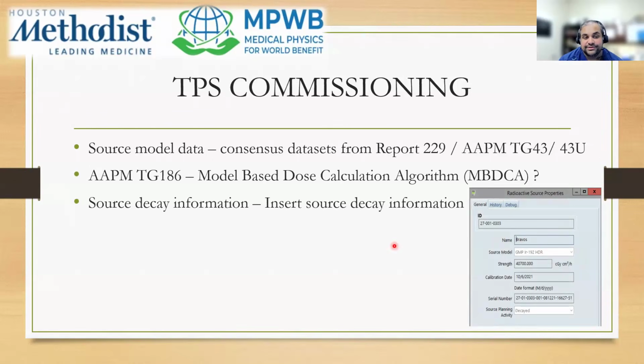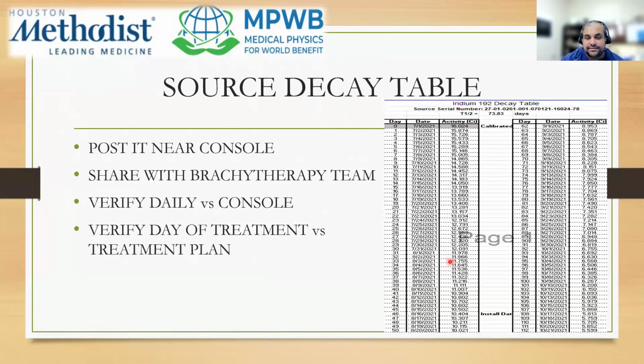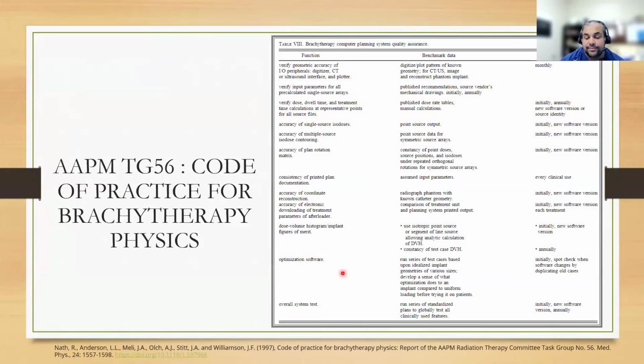You have to import your source decay information into your treatment planning system. This option, I know this is with Varian at least, lets you choose between decayed and nominal. The main difference is that if you leave it at nominal, then all your treatment plans will be done at the nominal activity of 10 curies. But if you leave it at decayed, then your treatment planning source strength on the day of the procedure should match the source decay table and the source decay that will be on your console.